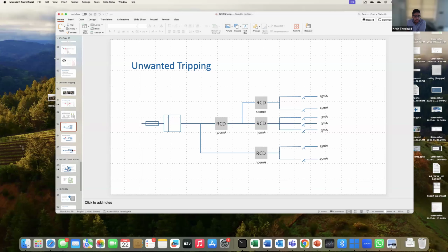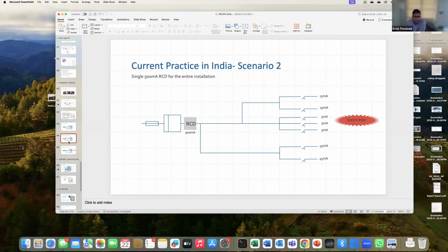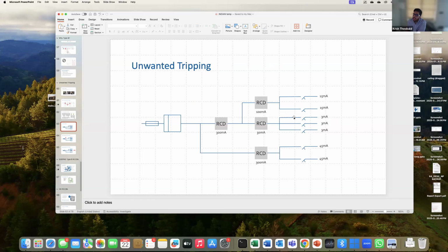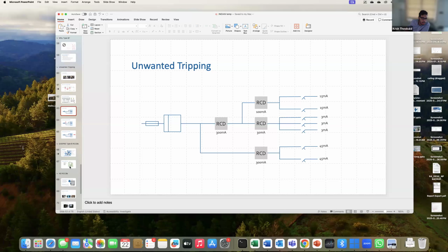Sure. Actually, I am just going to pull up Gerard's slides. So as you can see from the screen, like Gerard showed us, if you have a single RCD for the entire house and you put 30 milliampere, then it will give you nuisance tripping. If you put 500 milliampere, it will not provide you shock protection, additional protection. But the question here is, what do you need? If you have a TN system, you don't need fault protection from an RCD. You only need additional protection, and in certain cases, fire protection. So you have to sectionalize. My recommendation to you is use an RCD only where it is required. For example, if you're using a socket outlet, use a 30 milliampere RCD only on the socket outlet. Now, there are some slides about the nuisance tripping.